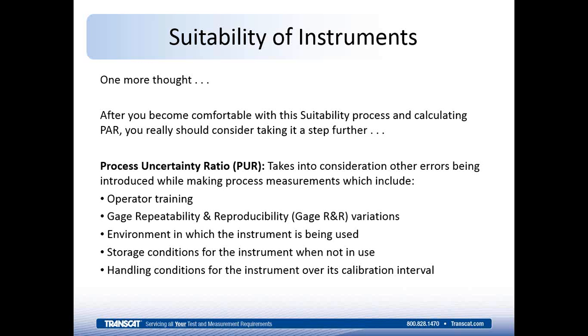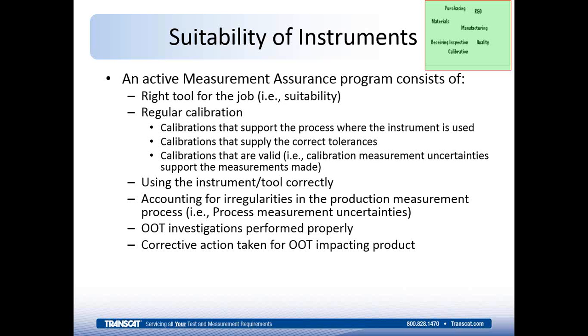And that's where we get back to that TAR, or what we call test uncertainty ratio, TUR. And whether those are healthy ratios as well between the instruments used to calibrate your instrument, making sure those are healthy ratios of 4 to 1 or better. So besides regular calibration, using the instrument or tool correctly, accounting for irregularities in the production measurement, process measurement uncertainties as opposed to just accuracy of the instrument being used, and then out of tolerance investigations, are those performed correctly?